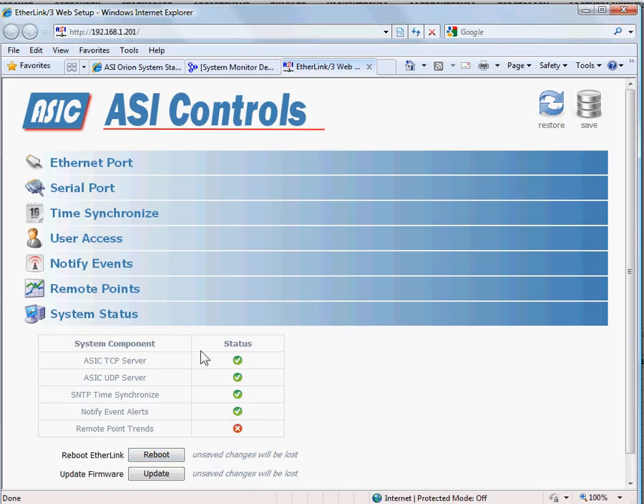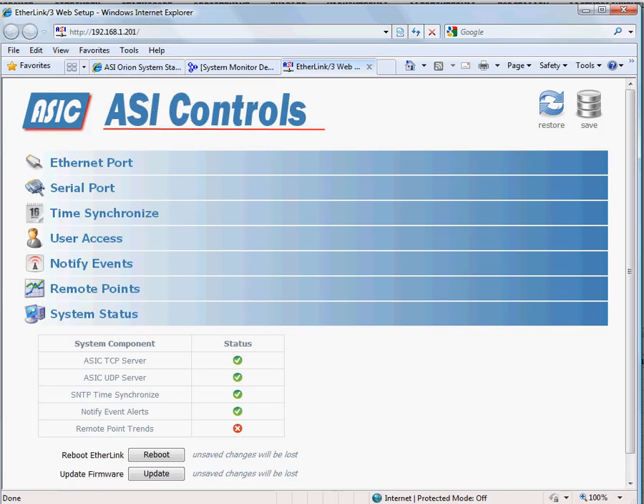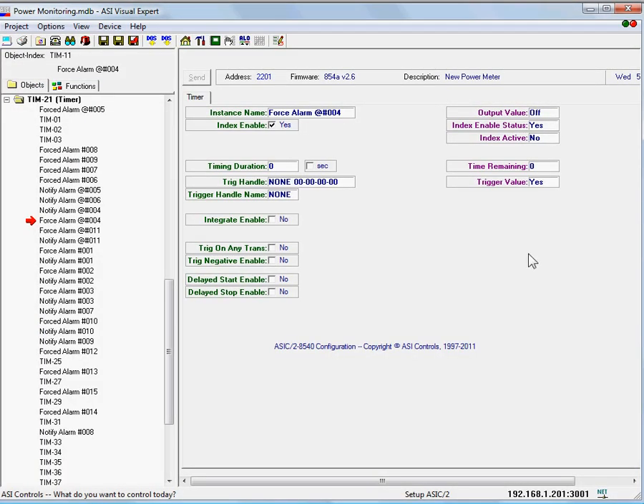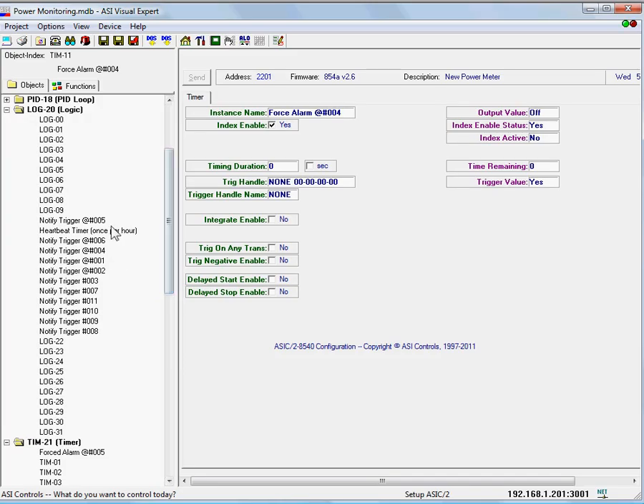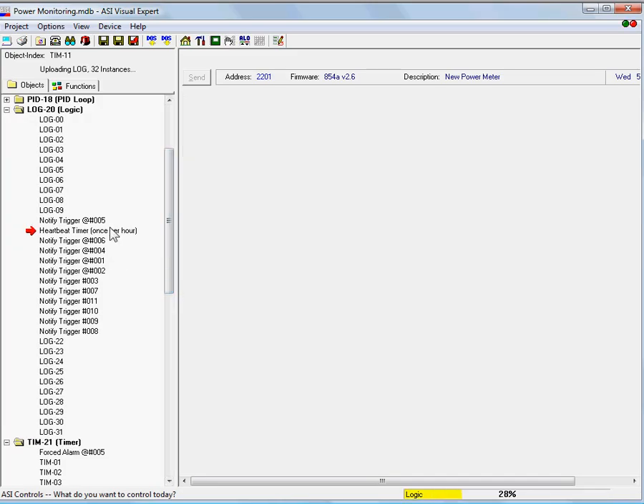We'll now look quickly in expert to see how it's set up on that end. We have a heartbeat set up. What it does is it's a logic object that looks at the clock, and it transitions any time the clock is greater than 30. So once per hour, we'll get a heartbeat.